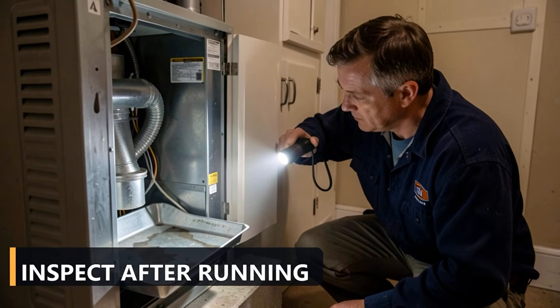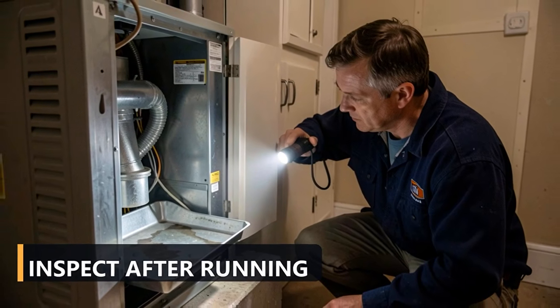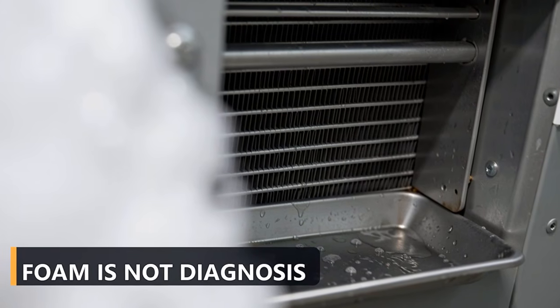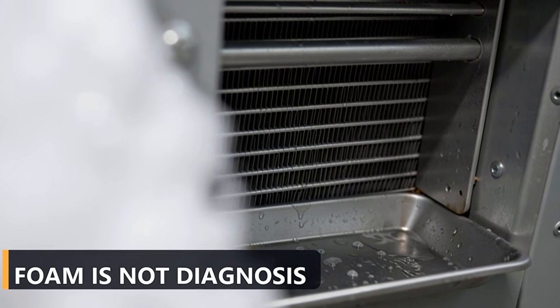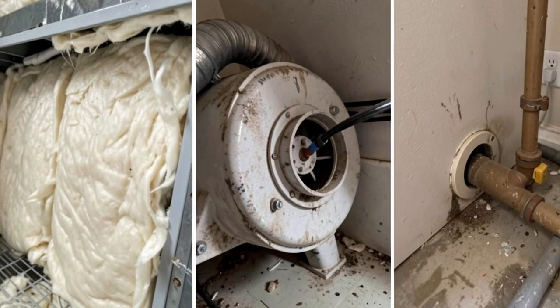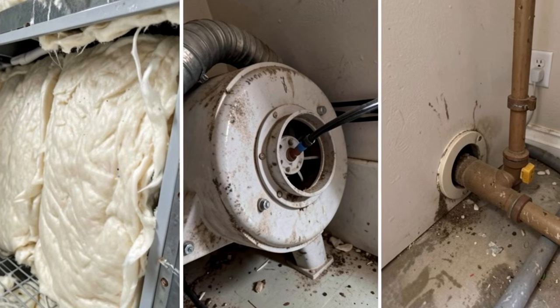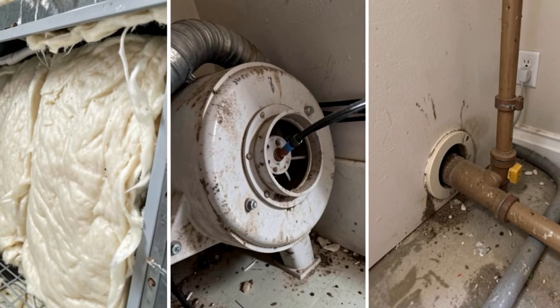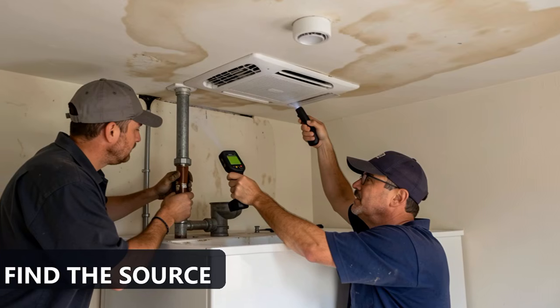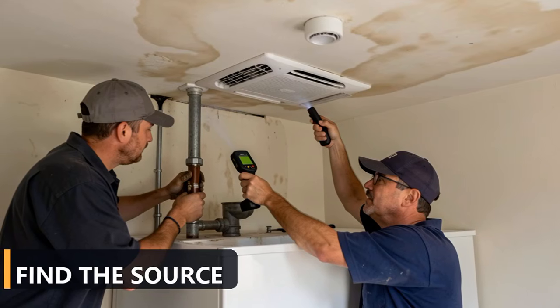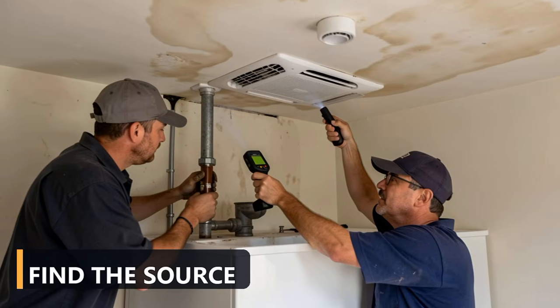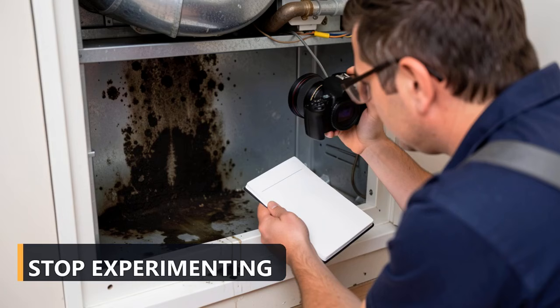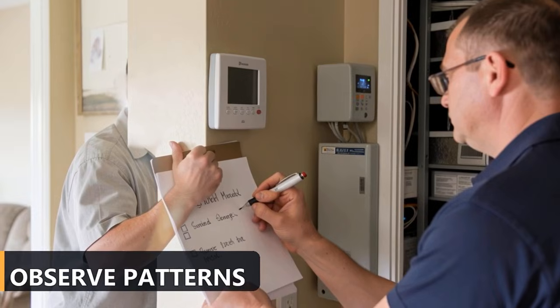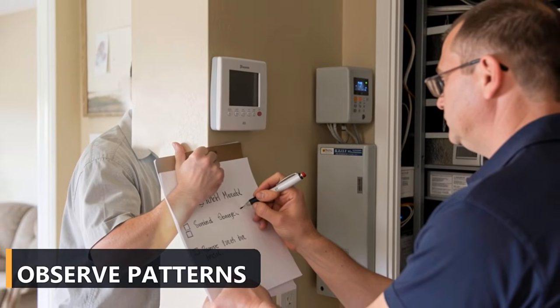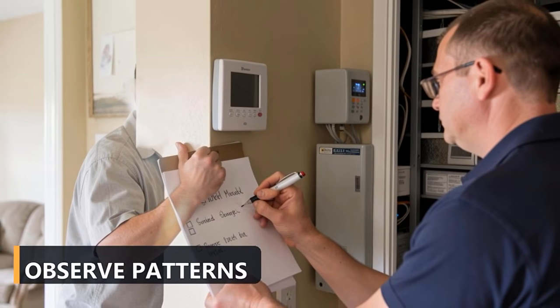There is also a health clue the bottle cannot diagnose. A musty odor can come from a wet coil or drain, but also from damp insulation, a soiled blower, a plumbing trap, or moisture elsewhere in the building. Masking the smell does not identify its source. If contamination covers a large area or returns quickly, stop experimenting. Document where water appears, when the odor is strongest, and whether it changes when the fan runs. Those details help locate the actual failure instead of treating the wrong surface.